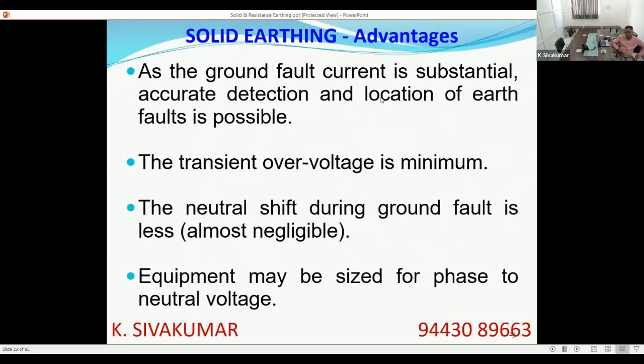And as we have seen, the ground fault current is substantial. Accurate detection and location of earth fault is possible. Transient overvoltage is minimum. The neutral shift is negligible. Equipment, normally the insulation sizing: since you are solidly grounding the neutral, all the phase to earth insulation downstream of such a network can be insulated for phase to neutral voltage only. So the insulation cost comes down greatly.